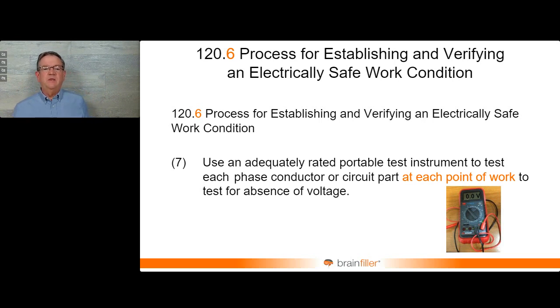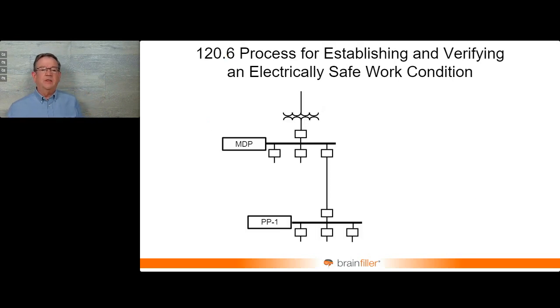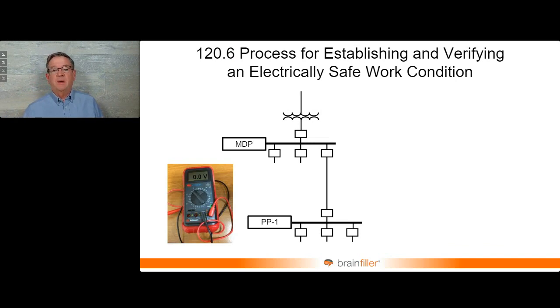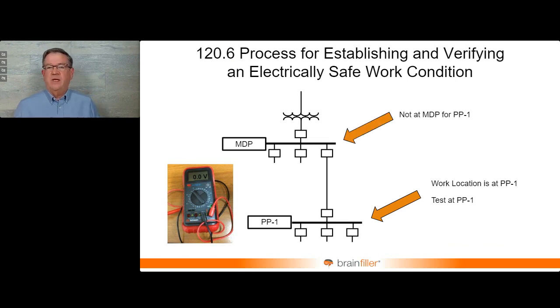So what this means is if you were going to be conducting work at panel PP1, down towards the bottom here, you test for absence of voltage at the work location. Testing up at MDP, I mean, you can do that if you want, but that is not going to qualify as testing for absence of voltage for work being performed down at PP1.